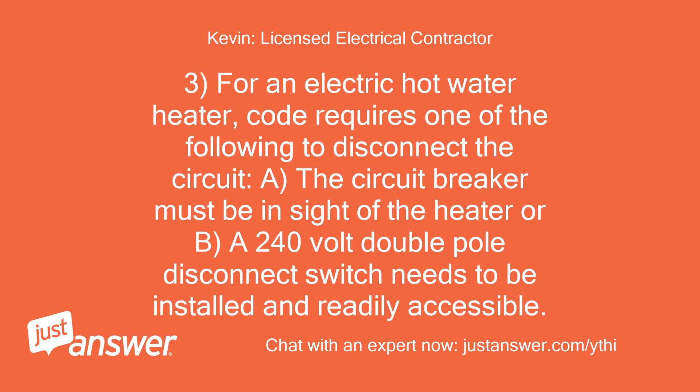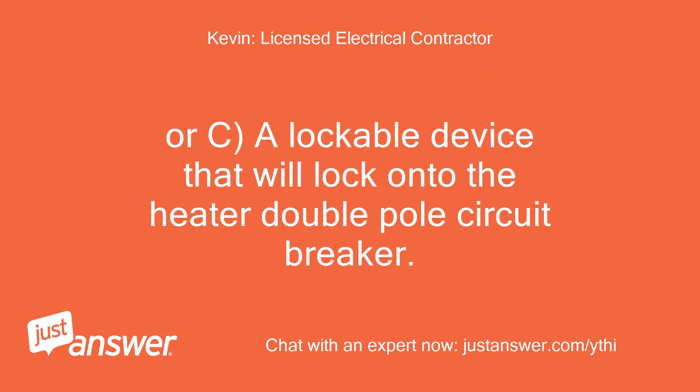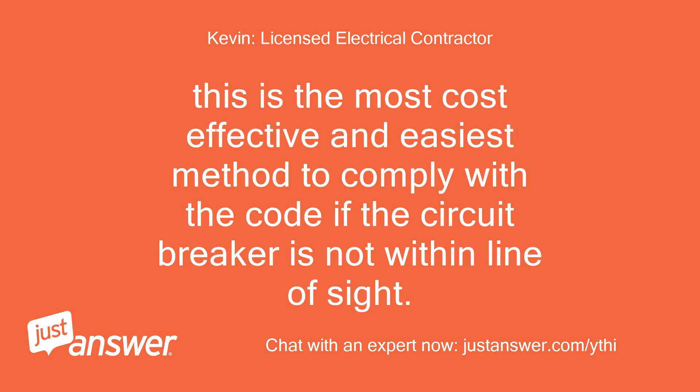For an electric hot water heater, code requires one of the following to disconnect the circuit: A) The circuit breaker must be in sight of the heater, or B) A 240-volt double-pole disconnect switch needs to be installed and readily accessible, or C) A lockable device that will lock onto the double-pole circuit breaker. This is the most cost-effective and easiest method to comply with the code if the circuit breaker is not within line of sight.